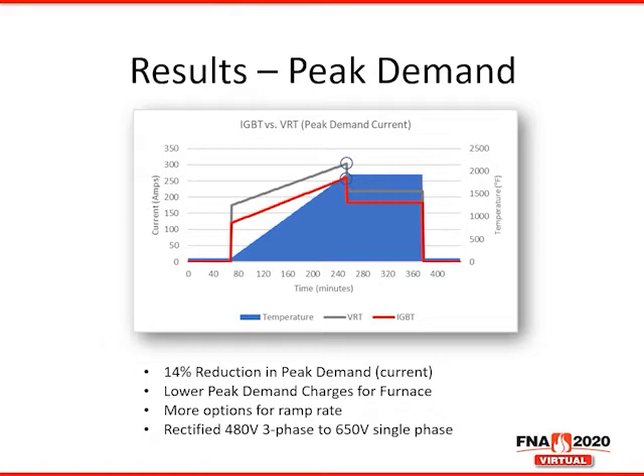This correlates to lower peak demand charges for the furnace, and you can imagine a cumulative reduction the more of these controls you have in your facility. This also offers you the ability to change your ramp rate. You can get up to heat faster for the same rate and be more productive, or you can focus on the peak demand, really drop that down in your facility.